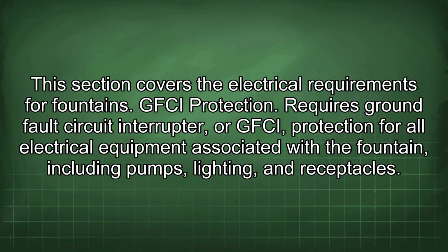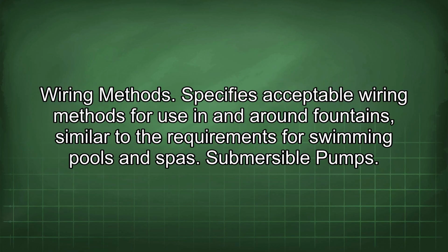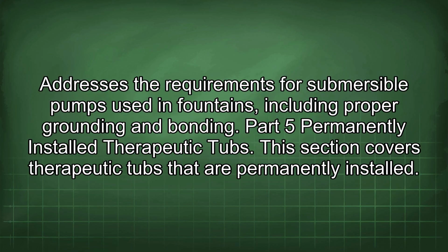Part 4. Fountains. This section covers the electrical requirements for fountains. GFCI protection. Requires ground fault circuit interrupter, or GFCI, protection for all electrical equipment associated with the fountain, including pumps, lighting, and receptacles. Wiring methods. Specifies acceptable wiring methods for use in and around fountains, similar to the requirements for swimming pools and spas. Submersible pumps. Addresses the requirements for submersible pumps used in fountains, including proper grounding and bonding.